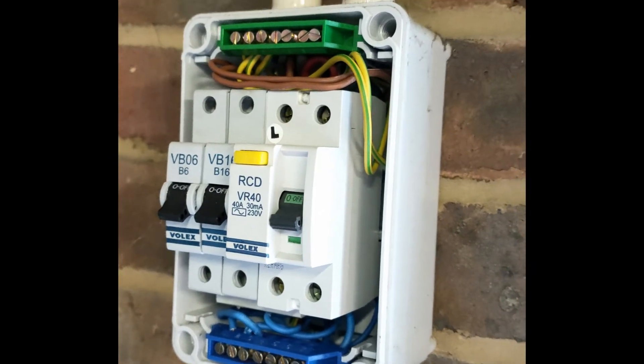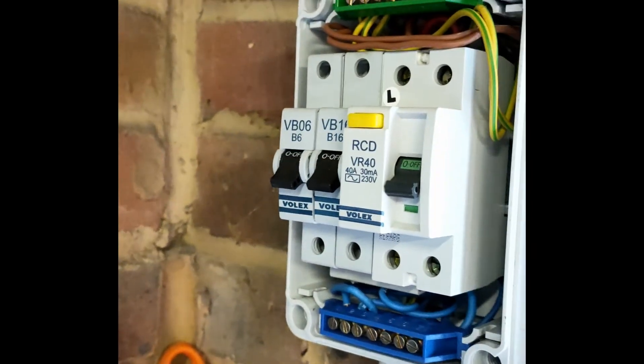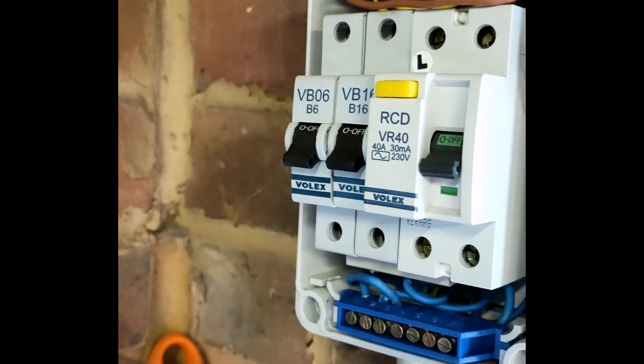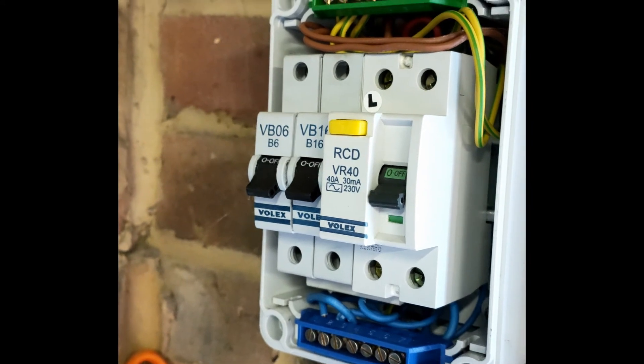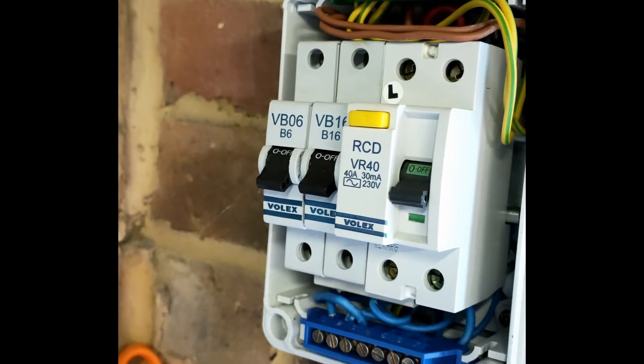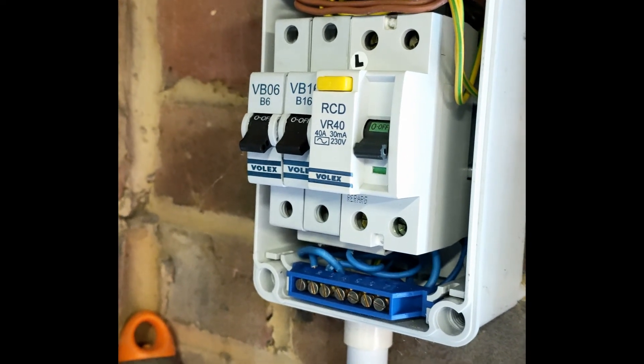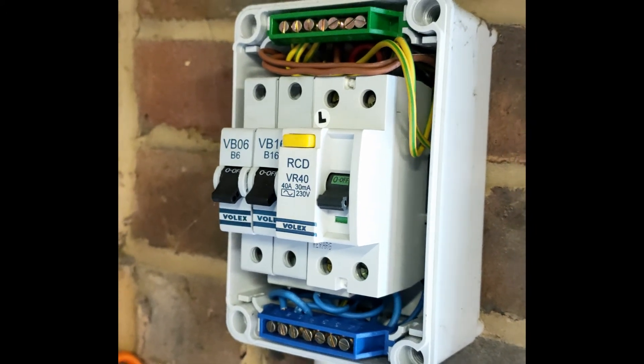I'll do the insulation resistance test next and then we'll liven it up. The insulation resistance — top of the MCB to the earth bar — came out greater than 2,000 MΩ on the tester. Top of the MCB to neutral was again absolutely fine, greater than 2,000. So I'm reasonably happy with the IR testing. I'm going to close this up and liven it up.